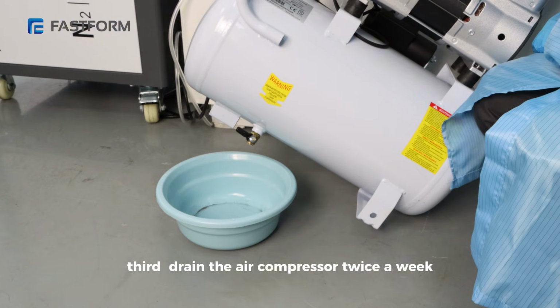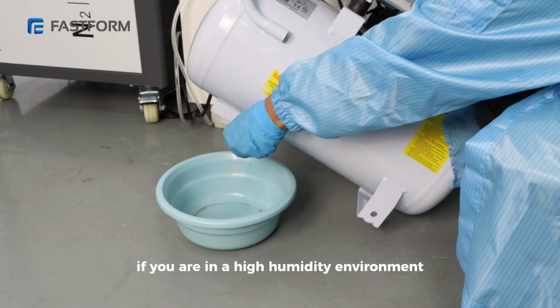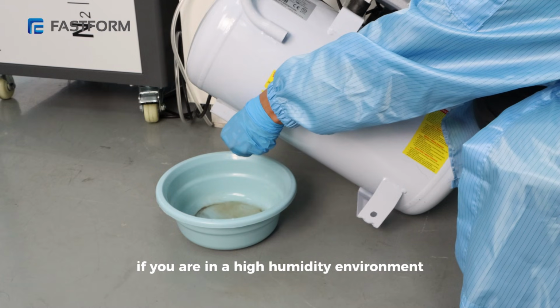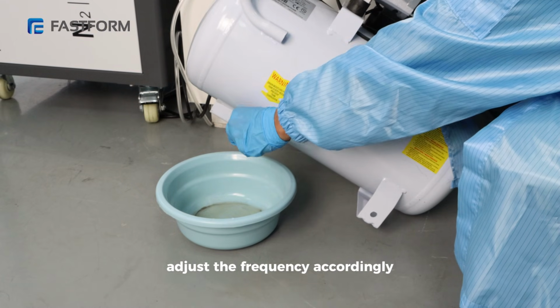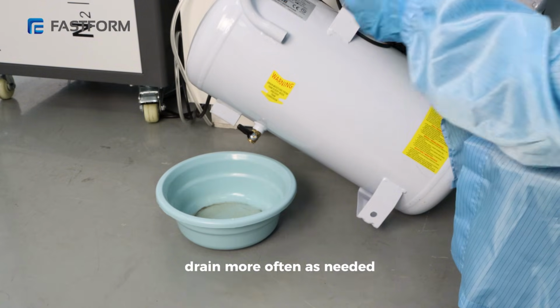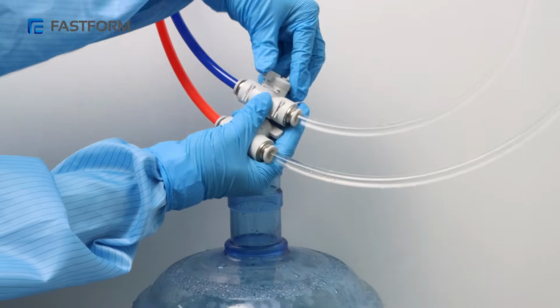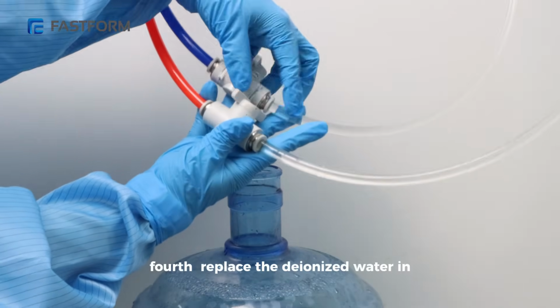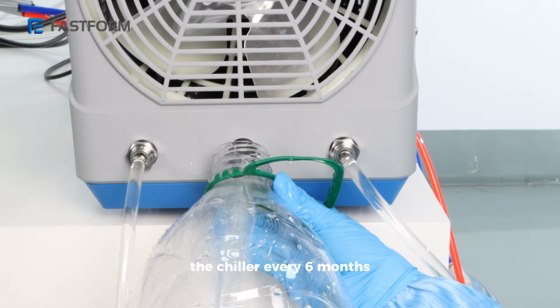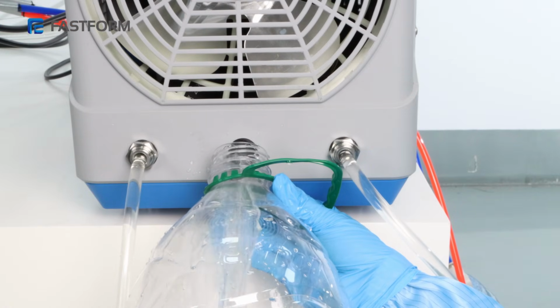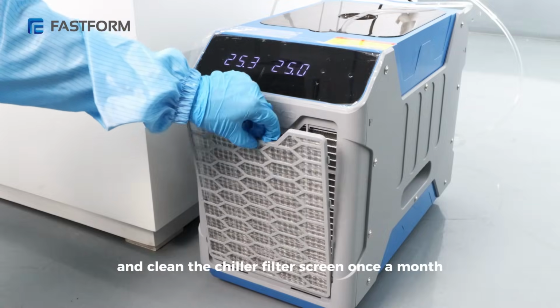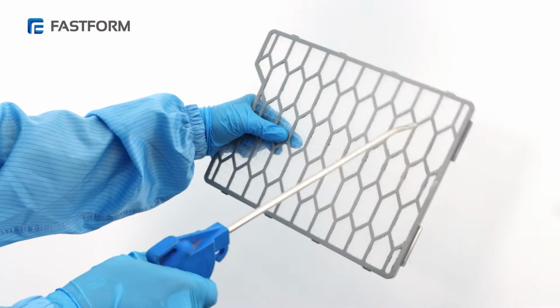Third, drain the air compressor twice a week. If you are in a high humidity environment, adjust the frequency accordingly. Drain more often as needed. Fourth, replace the deionized water in the chiller every 6 months. And clean the chiller filter screen once a month.